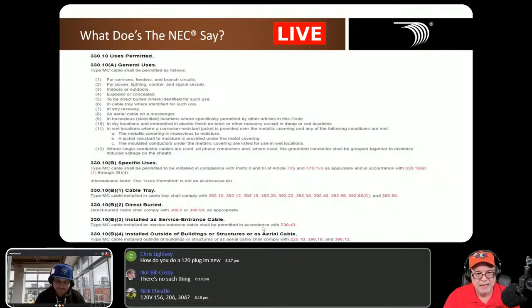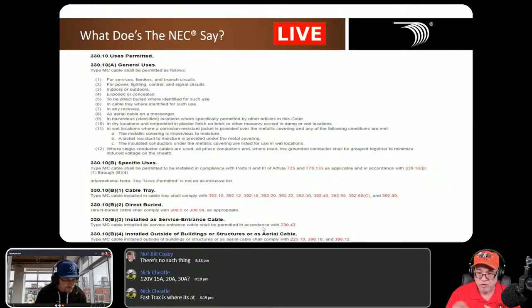All right, next is 330.10(B)(2), direct burial. This gives permission to take MC cable and directly bury it into the earth, but there are caveats. Direct burial cable shall comply with 300.5, which covers all the rules for placing cable underground. MC cable is fine to be direct buried if it's listed for such and marked as such, but it also has to comply with 300.5. This is for applications 1,000 volts and less. 300.50 would cover over 1,000 volt applications.